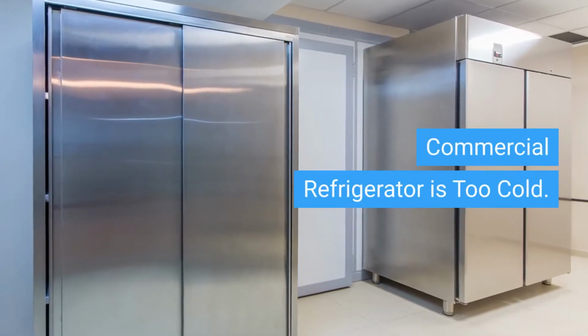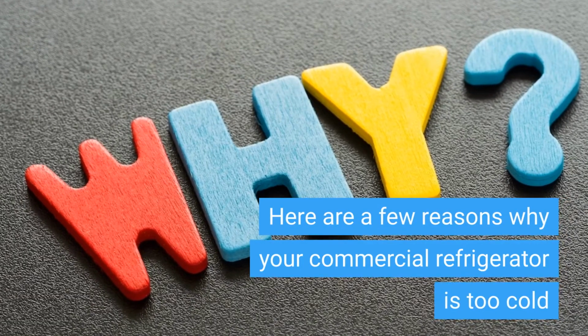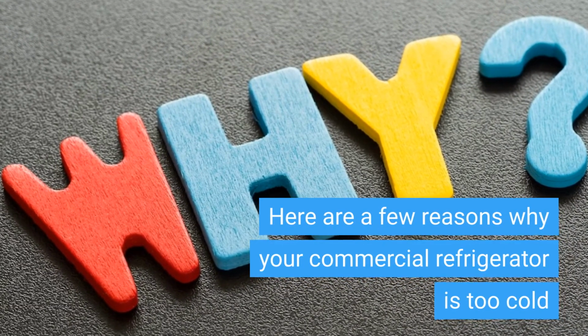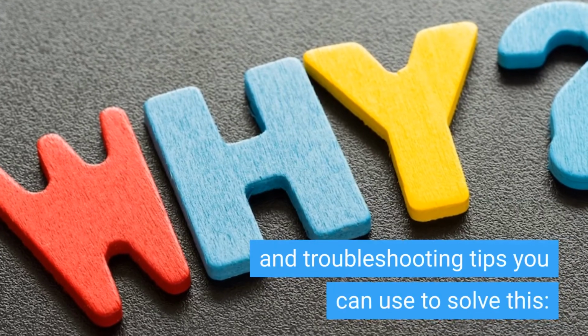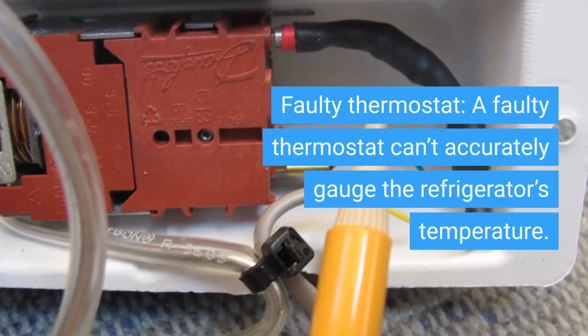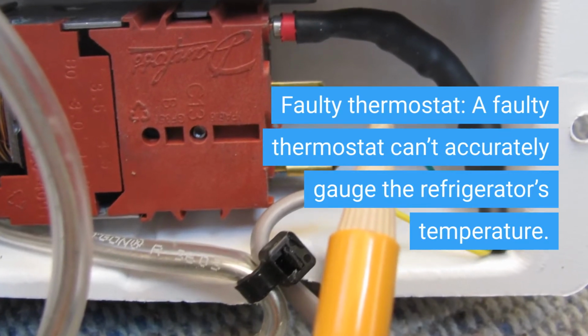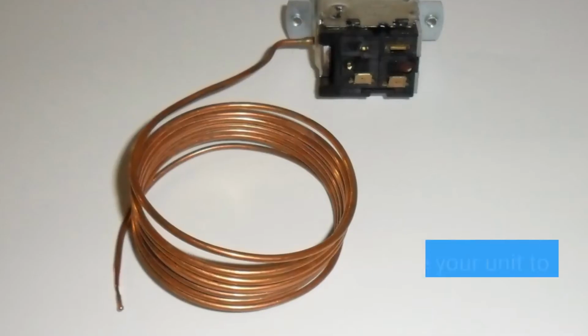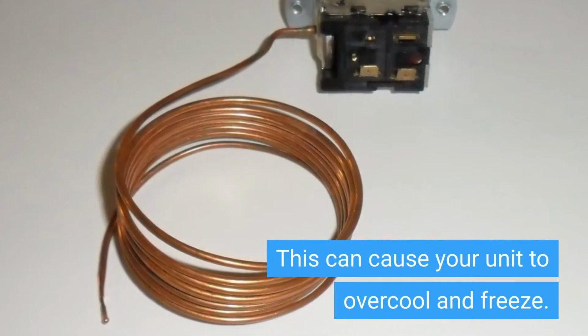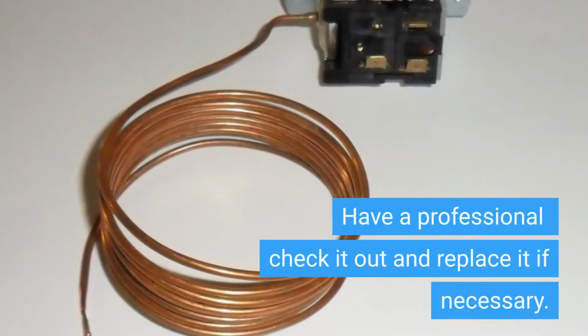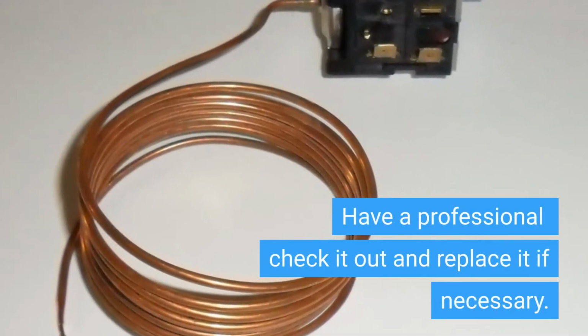Commercial refrigerator is too cold. Here are a few reasons why your commercial refrigerator is too cold and troubleshooting tips you can use to solve this. Faulty thermostat. A faulty thermostat can't accurately gauge the refrigerator's temperature. This can cause your unit to overcool and freeze. Have a professional check it out and replace it if necessary.